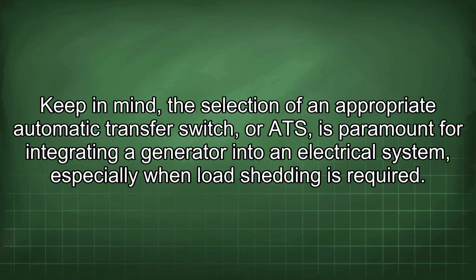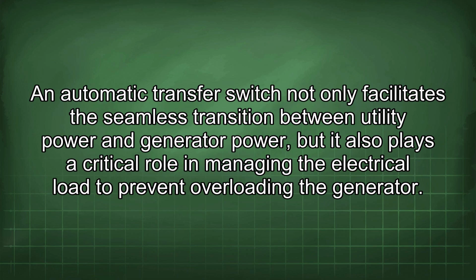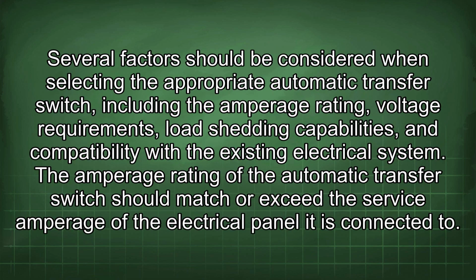Keep in mind the selection of an appropriate automatic transfer switch, or ATS, is paramount for integrating a generator into an electrical system, especially when load shedding is required. An automatic transfer switch not only facilitates the seamless transition between utility power and generator power, but it also plays a critical role in managing the electrical load to prevent overloading the generator. Several factors should be considered when selecting the appropriate automatic transfer switch, including the amperage rating, voltage requirements, load shedding capabilities, and compatibility with the existing electrical system.